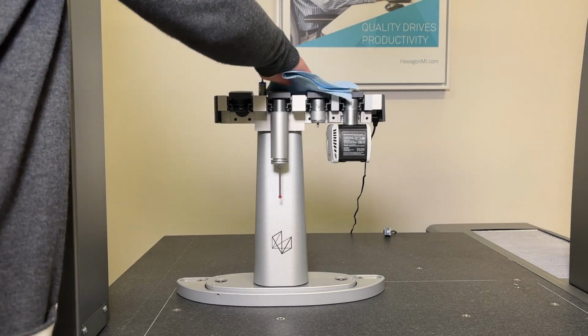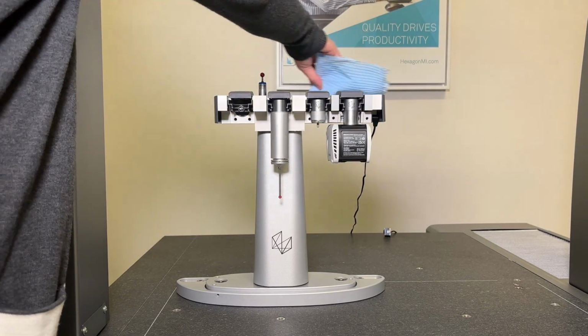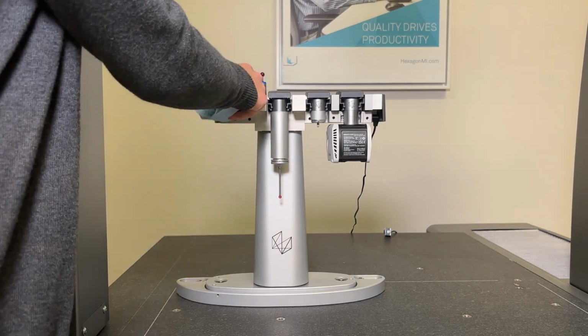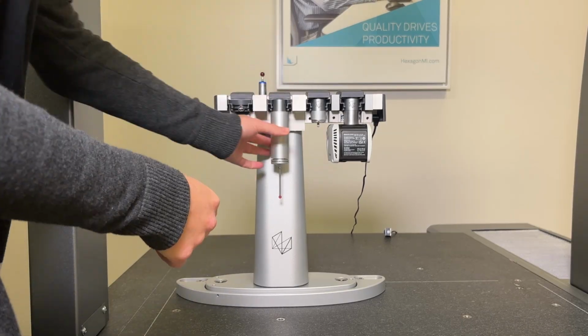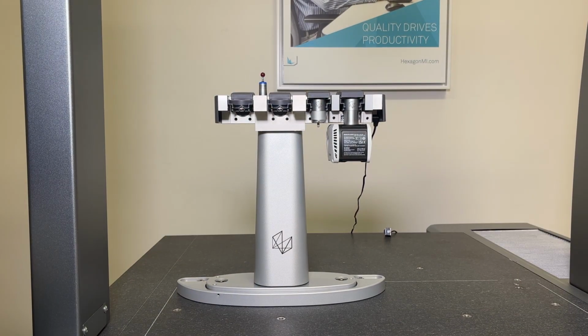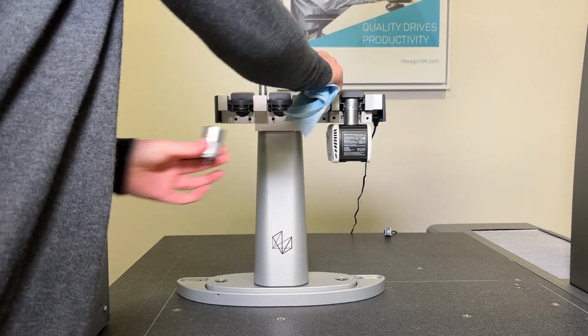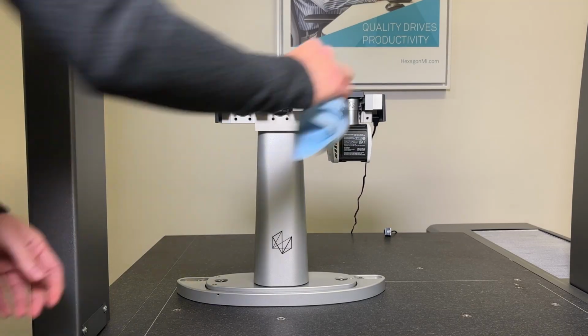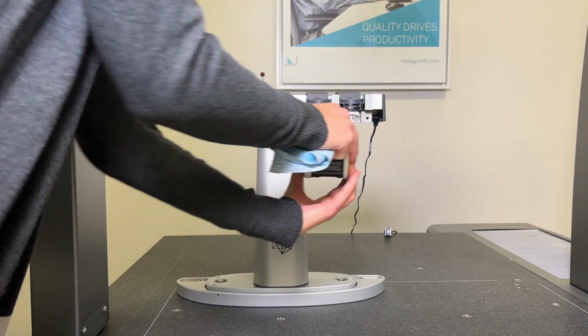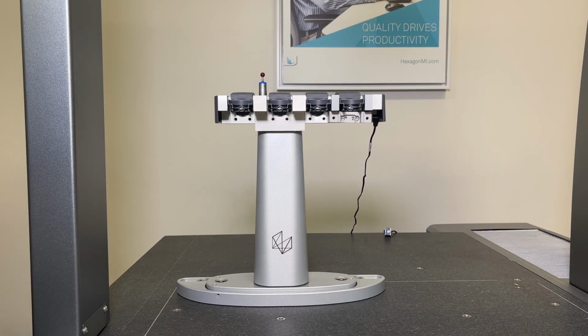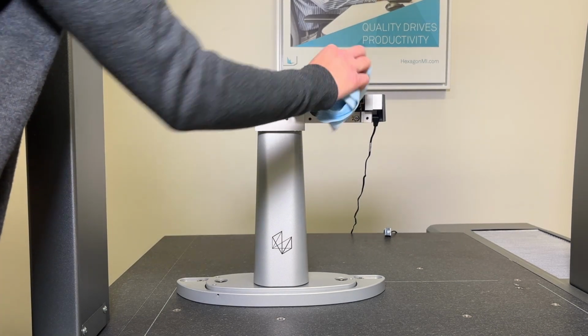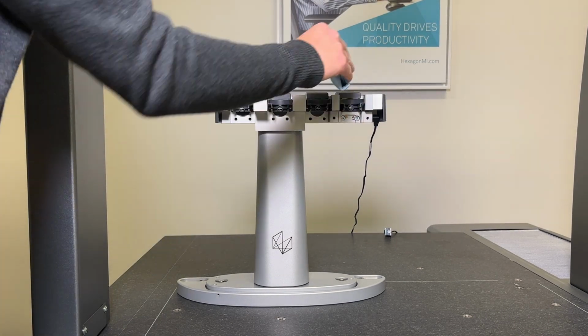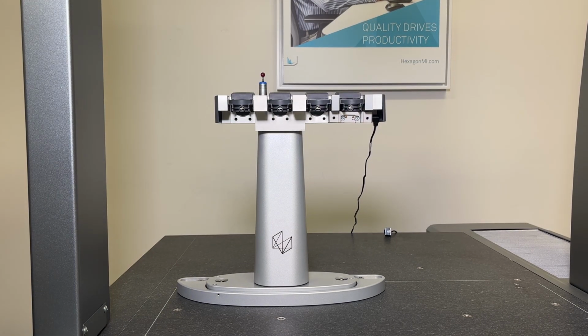First, you need to get your rack ready for calibration. You'll want to go in with a lint-free towel and dust everything off. You'll then want to push back the covers, dust off there as well, and remove all of the attachments. Find a safe space to store these while we're running through the calibration to make sure they're not in the way and will not get damaged.